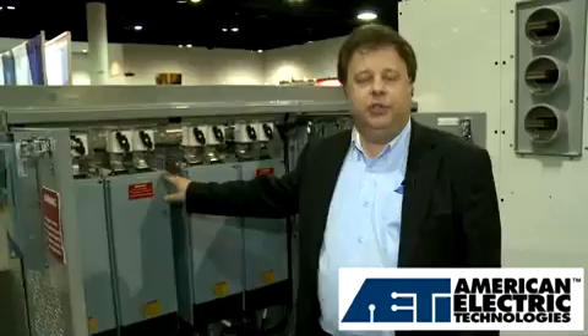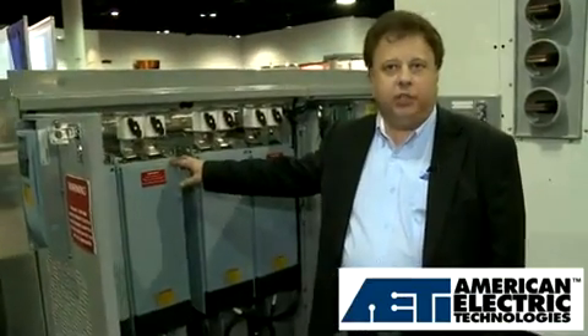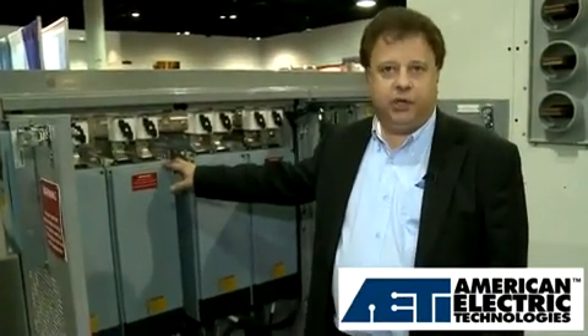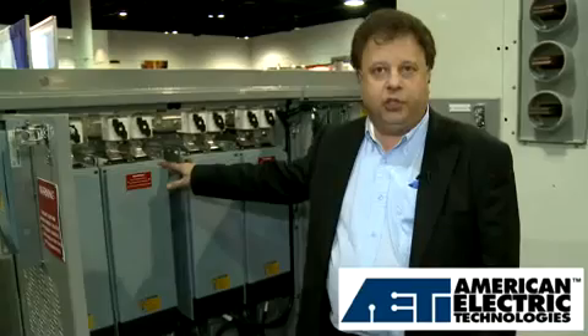The EWT turbine is a 900 kilowatt model right now. It'll be extensible to a 2 megawatt permanent magnet system in the future. But today it is essentially a 20-foot wide 42 pole motor that is feeding into two sections of our converter here. So it is a 0 to 10 hertz motor essentially, which gets up converted to 60 hertz. It's a direct drive turbine, one of the first in the world.